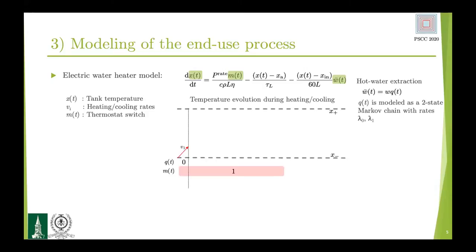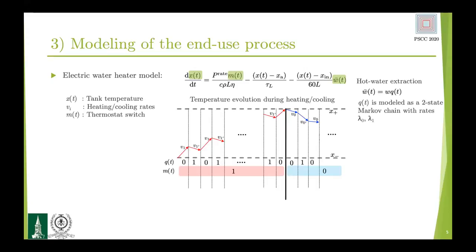We first look at how the temperature evolves inside the tank of an electric water heater. Electric water heaters are usually designed to operate within a narrow dead band, shown here as X minus and X plus. We can look at how the temperature evolves by looking at small time instances. For example, in the first interval starting from the on state — meaning the electric water heater is on but there is no water extraction, so Q is equal to zero — it's reasonable to assume that the temperature will increase with some rate V1. In the next time instance, because of water extraction, the temperature will momentarily decrease with some rate V1 prime. We can follow how the temperature evolves within the dead band until it reaches the boundary X plus, at which point it turns off, and then the temperature monotonically decreases, but depending upon whether extraction is present or not, the rates may be different.